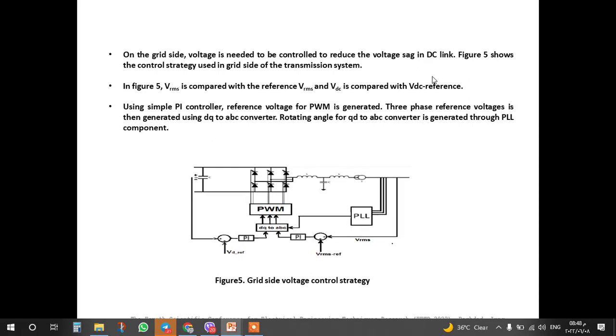However, the grid side voltage needs to be controlled to reduce the voltage sag in the DC link. Figure 5 shows the control strategy used on the grid side of the transmission system. In Figure 5, VRMS is compared with the reference VRMS and VDC is compared with the VDC reference. Using a simple PI controller, the reference voltage for pulse width modulation is generated. The three-phase reference voltage is then generated using the dq to abc converter. The rotating angle for the dq to abc converter is generated through the PLL component.